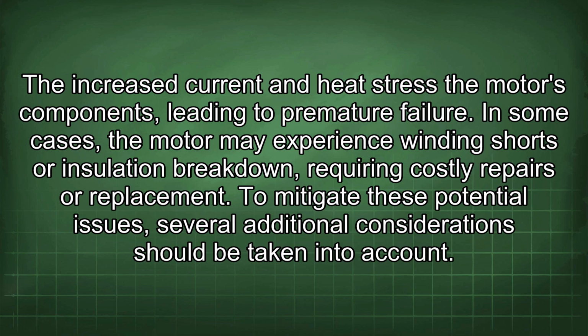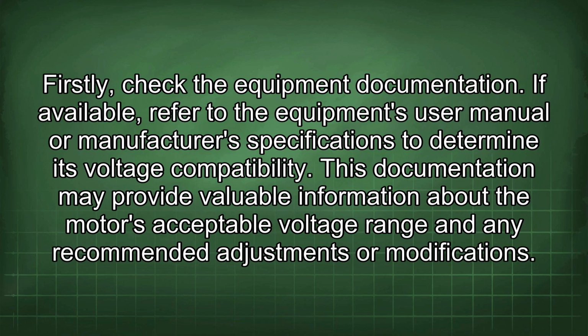To mitigate these potential issues, several additional considerations should be taken into account. Firstly, check the equipment documentation. If available, refer to the equipment's user manual or manufacturer's specifications to determine its voltage compatibility. This documentation may provide valuable information about the motor's acceptable voltage range and any recommended adjustments or modifications.